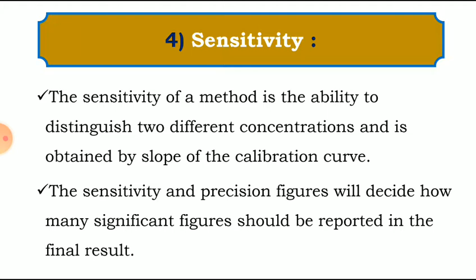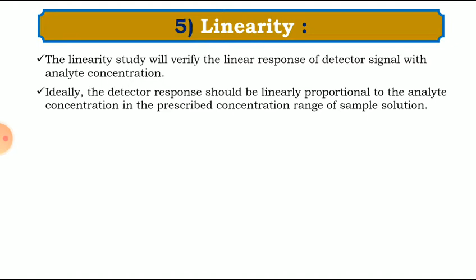Now, fifth number, linearity. The linearity study will verify the linear response of the detector signal with analyte concentration. Ideally, the detector response should be linearly proportional to the analyte concentration in the prescribed concentration range of the sample solution. The linearity study is performed using standard solution at 5 different concentrations. These 5 concentration levels detect the curvature on the calibration curve. For systematic linearity studies, each standard solution should be measured at least 3 times.